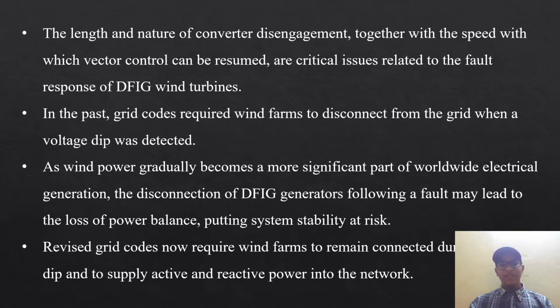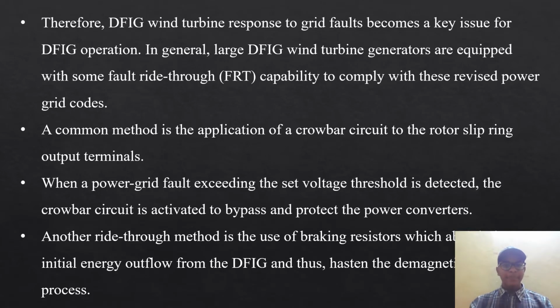The length and nature of converter disengagement, together with the speed with which vector control can be resumed, are critical issues related to the fault response of DFIG wind turbines. In the past, grid codes required wind farms to disconnect from the grid when a voltage dip was detected. As wind power gradually becomes a more significant part of worldwide electrical generation, the disconnection of DFIG generators following a fault may lead to the loss of power balance, putting system stability at risk. Revised grid codes now require wind farms to remain connected during the dip and to supply active and reactive power into the network. Therefore, DFIG wind turbine response to grid faults has become a key issue for DFIG operation.